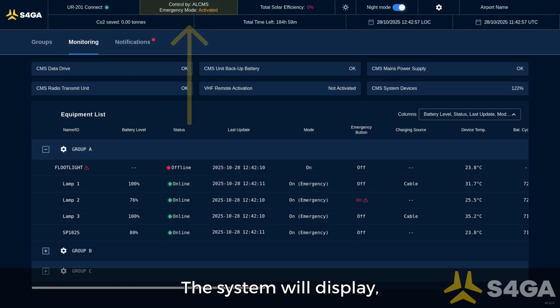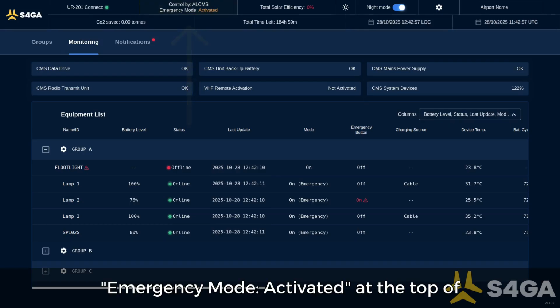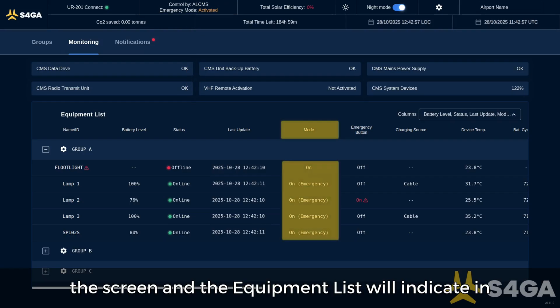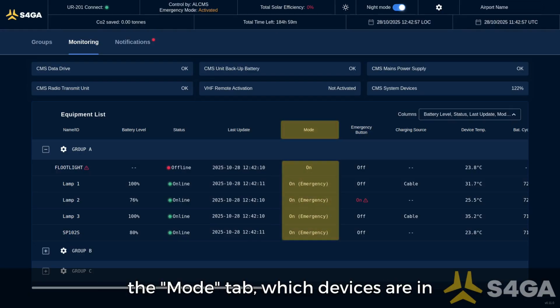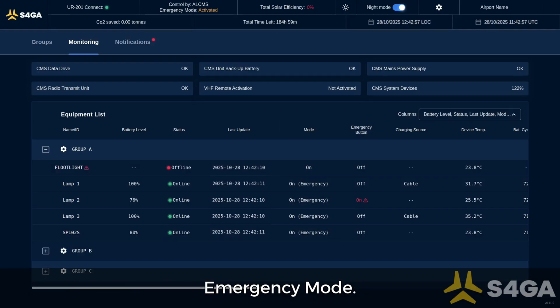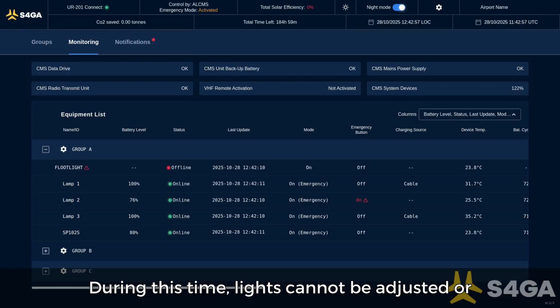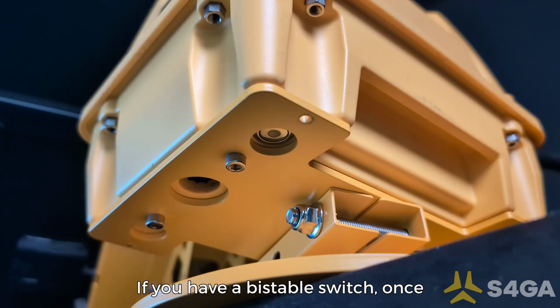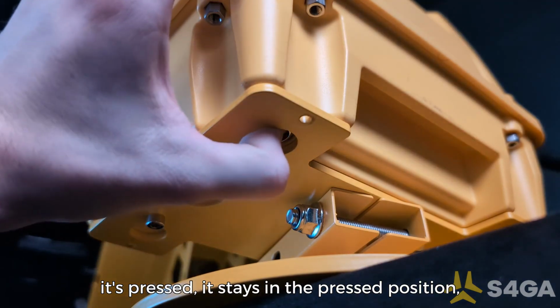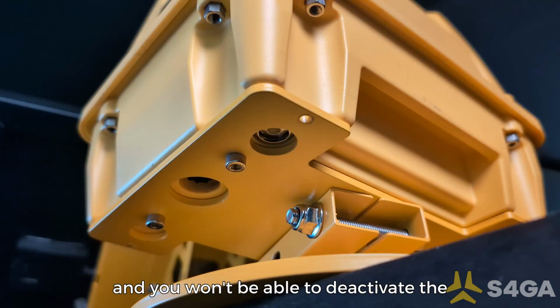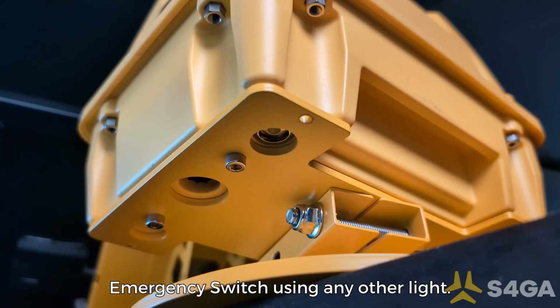The system will display Emergency Mode activated at the top of the screen, and the equipment list will indicate in the Mode tab which devices are in emergency mode. During this time, lights cannot be adjusted or turned off. If you have a bistable switch, once it's pressed, it stays in the pressed position, and you won't be able to deactivate the emergency switch using any other light.